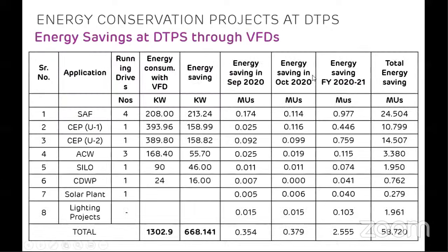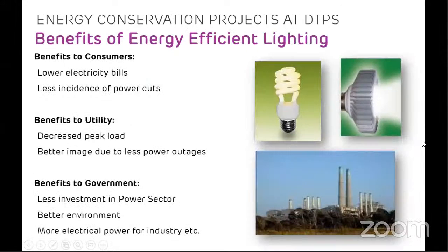This is a brief summary of energy savings achieved from various VFDs and other projects in our plant. There are 4 sealer fans, with the kilowatt rating I just explained. They gave 24 million units. Unit is kWh, so 24 million kWh of saving from seal air fan motors only. From the condensate extraction pump, 10 million units. If we go on adding solar plant and lighting project benefits, it comes out to roughly 60 million units till date. This is data up to the end of October 2020. 60 million units of energy is saved till now. And 668 kilowatt is the kilowatt saving.